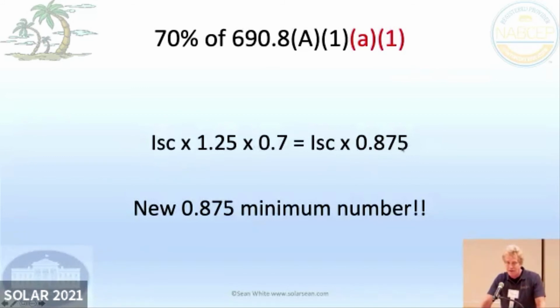Sometimes too, they could be like, do you really want to use the smallest possible wire that you can? Because you'll have so much voltage drop. But as PV is getting cheaper and cheaper, and the way it's going down, I mean, it'll be free. When PV gets free, then we just worry about our wire costs. And then maybe we will start using really super small wires. A lot of times I've even done calculations for wire sizing where I could have used a 14 gauge wire, where mostly people use 10 gauge wires, but you do the calculation and sometimes it could have been a 14.